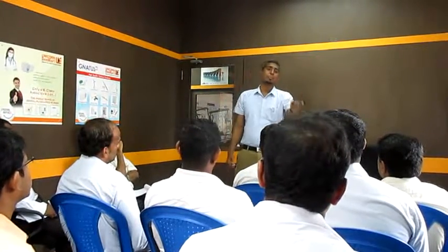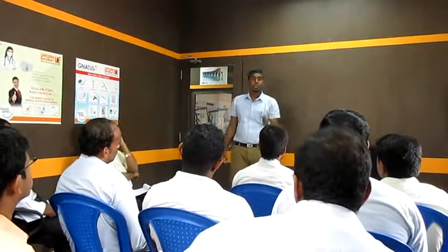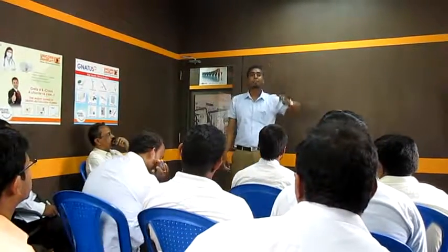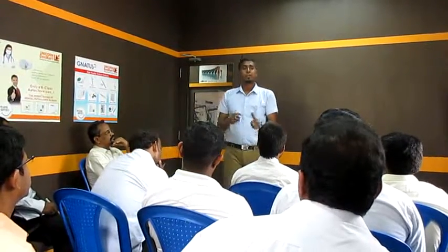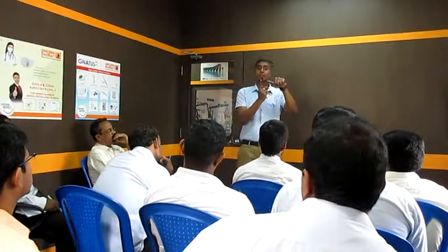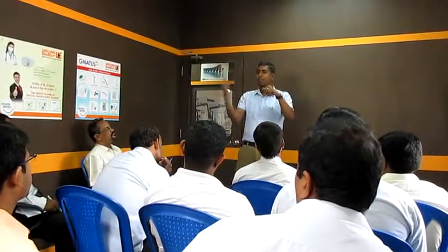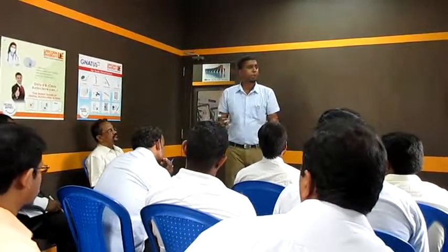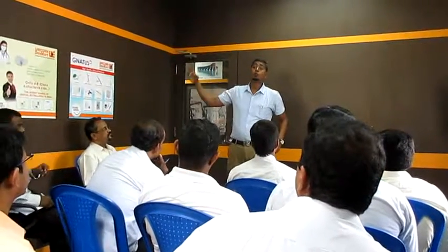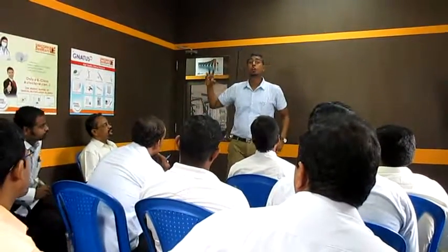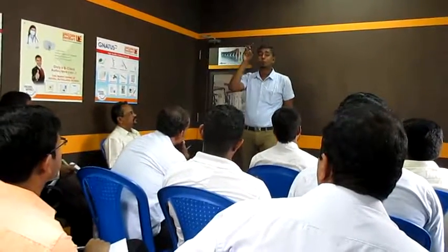That is why AERB doesn't want you to use a machine in which you set one parameter and it gives you something else. Why? Because you cannot see radiation. You cannot measure radiation in the air. So what will happen? You are giving more dose to the patient and putting the patient at risk. You are putting yourself at risk also. So AERB doesn't want this.